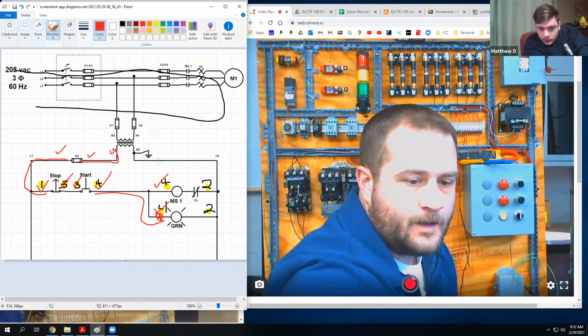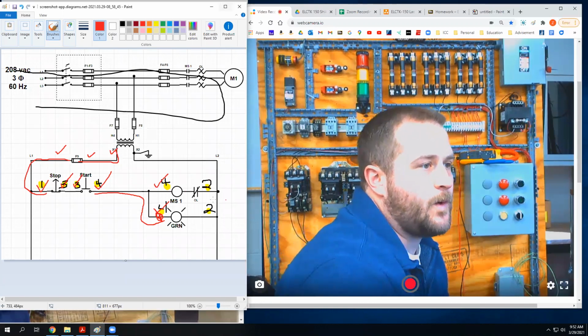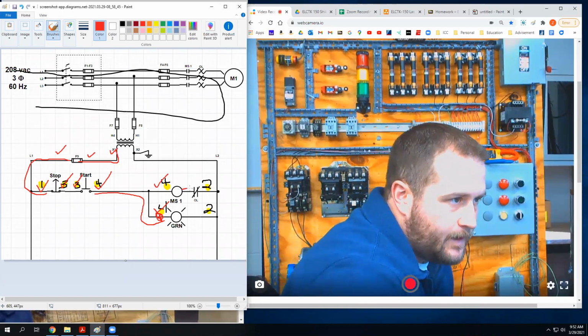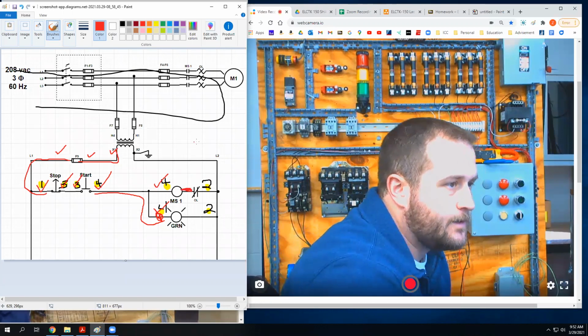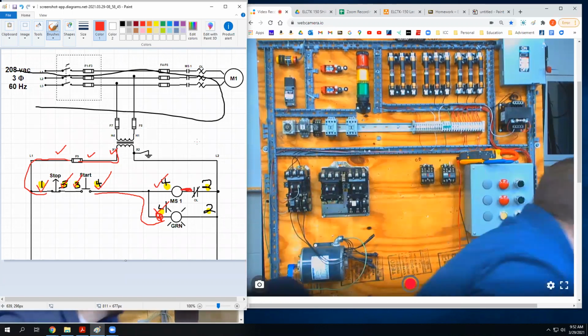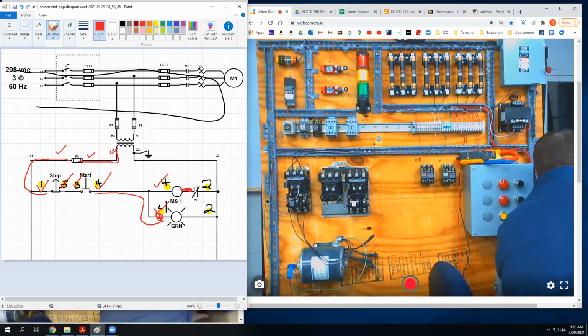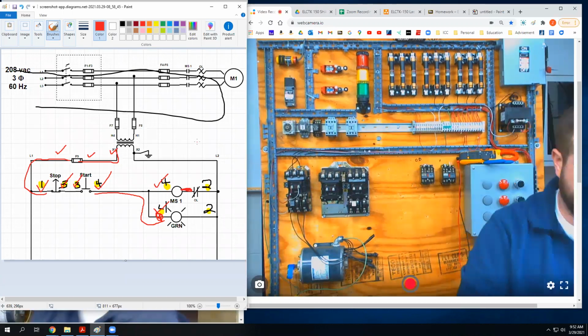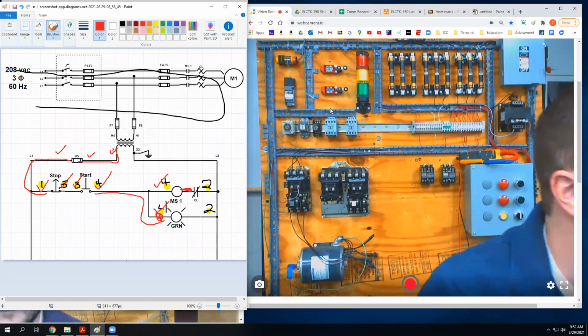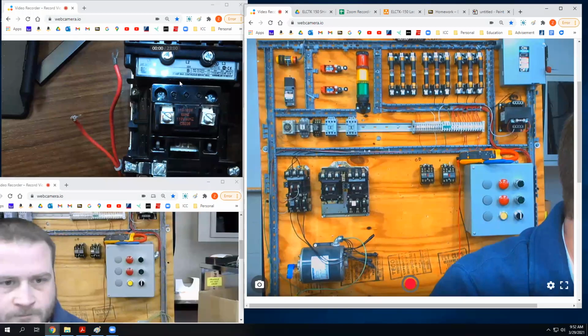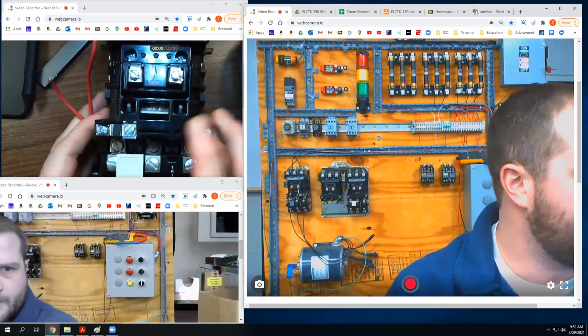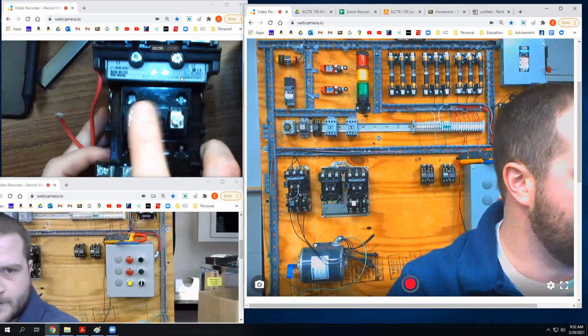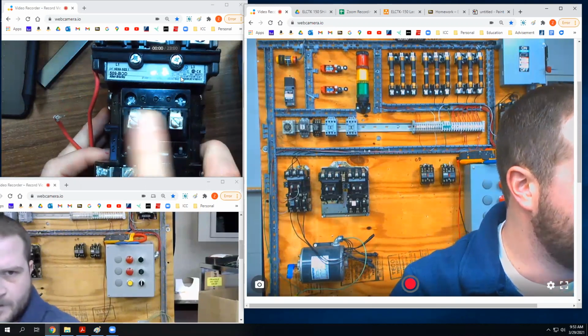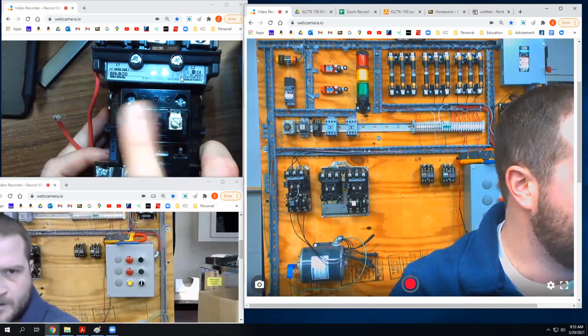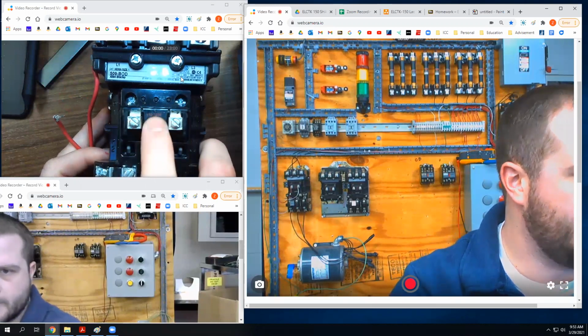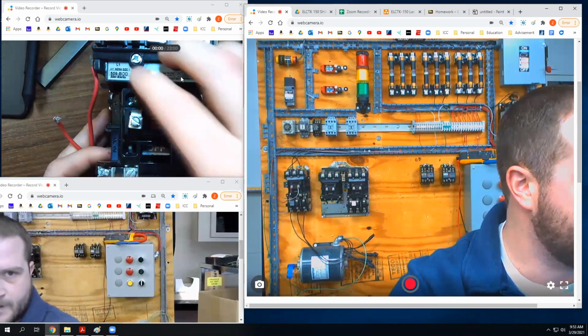Yes, it is. And just to clear that up, this little bitty number 2 wire is on your motor starter. It is coming off of this terminal on this. What is this thing called? It's the coil. That's what creates the electromagnetism that holds the contacts together.